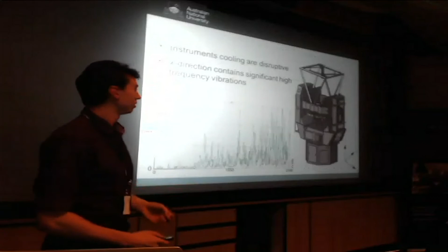The instruments, which are along this truss here, have to cool, and their cooling systems are just as disruptive as moving the telescope itself. So once they're finished cooling, the vibration dies down below what we can detect in the baseline spectra. So we recommend that all the cooling be done first for all the instruments to be used, and then the laser gets turned on to avoid those two interfering with each other.